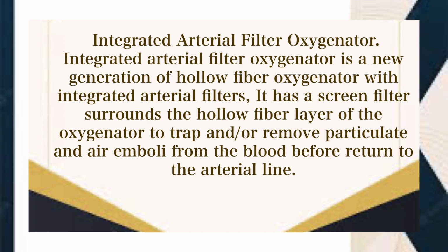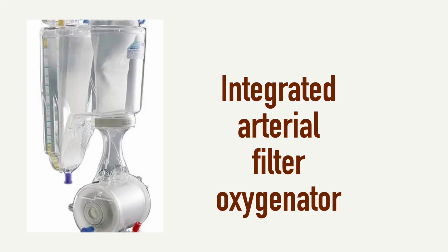Integrated arterial filter oxygenator. The integrated arterial filter oxygenator is a new generation of hollow fiber oxygenator with an integrated arterial filter. It has a screen filter surrounding the hollow fiber layer of the oxygenator to trap and remove particulate and air emboli from the blood before it returns to the arterial line, as shown in this figure.